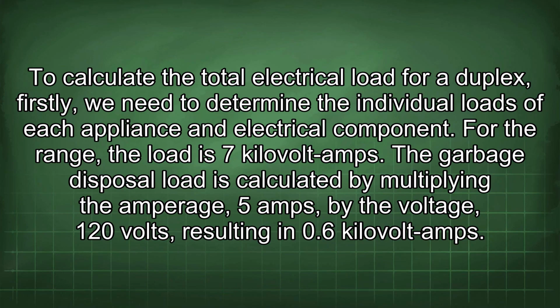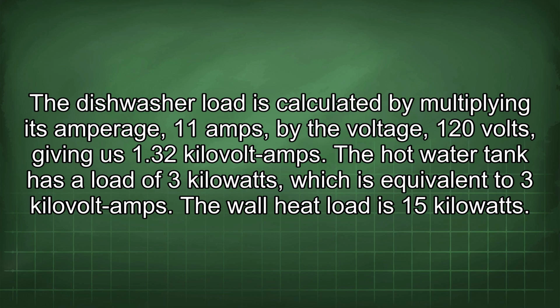To calculate the total electrical load for a duplex, firstly we need to determine the individual loads of each appliance and electrical component. For the range, the load is 7 kVA. The garbage disposal load is calculated by multiplying the amperage, 5 amps, by the voltage, 120 volts, resulting in 0.6 kVA. The dishwasher load is calculated by multiplying its amperage, 11 amps, by the voltage, 120 volts, giving us 1.32 kVA. The hot water tank has a load of 3 kilowatts, which is equivalent to 3 kVA.